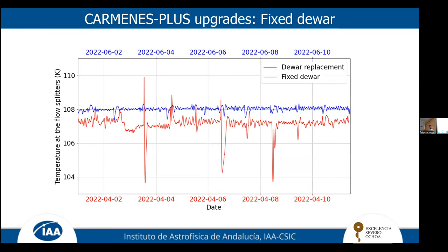And the temperature image that I want to show you: in red, we have previously, before this upgrade, refilling the bottle when we replaced this dewar every morning. We can see that every day there's a huge jump on the temperature, which basically resets the system every day, and this reflects directly on the radial velocity measurements. After we implement this fixed dewar, we have the blue line that is quite more stable. We have still some instabilities, but it's in another league, let's say, okay?